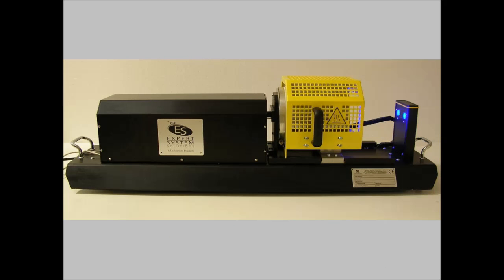Welcome to this short presentation of the Horizontal Optical Dilatometer Misura LT. The Horizontal Optical Dilatometer was first developed by Expert System Solution in the year 2002, and it is protected by two international patents. The design is completely innovative, and it is based on two microscopic optics with very high magnification, which frame both the ends of the sample.